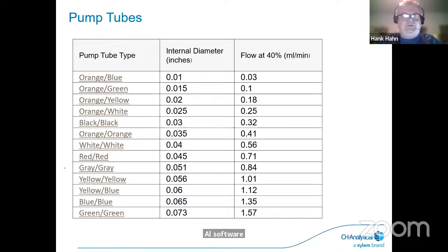Someone fortunately sat down and looked at the different internal diameter and flow rates of the pump tubes that are used by the varying chemistries. So I just included this to show the multiple pump tubes that we do use. And here's an example of pump tubes used in the ammonia TKN application. You have the orange green for air injection. You have yellow yellow for sample pull. You have black black for debubbler pull.